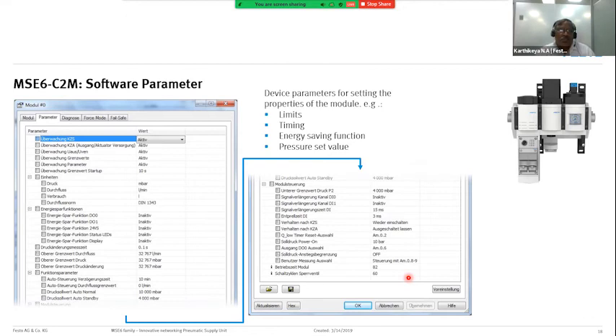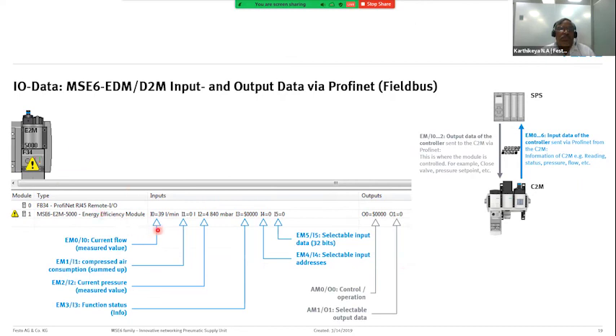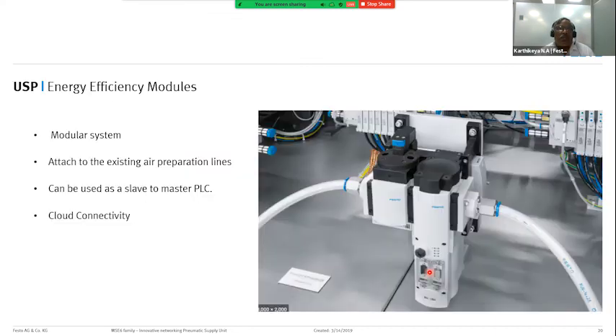These modules can be parameterized via software itself, where you can define different pressure units and the time of shutting off the valve. And you can also see via the software itself what pressure, flow, and consumption has happened to the process. You can also give control enable signals from your external inputs. On the energy efficiency modules, on the USP part, it is a modular system with intelligence, and you can directly use it on your existing air preparation units. The system can be used as a slave module to your existing master PLCs, and you have cloud connectivity. Thank you.